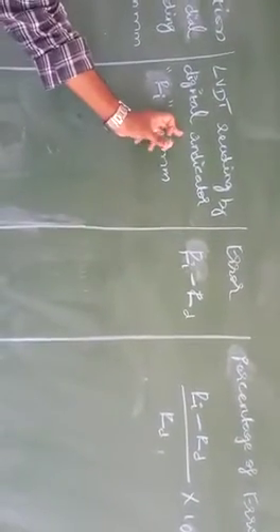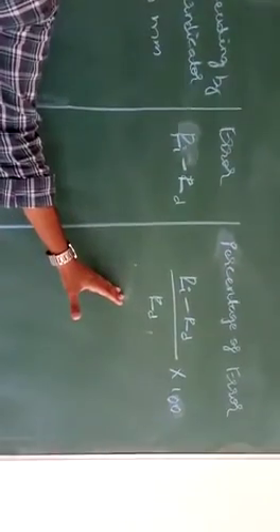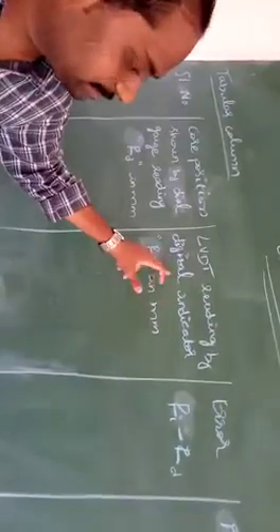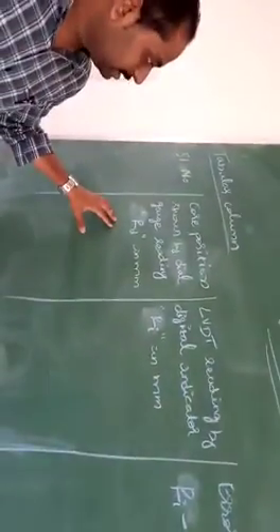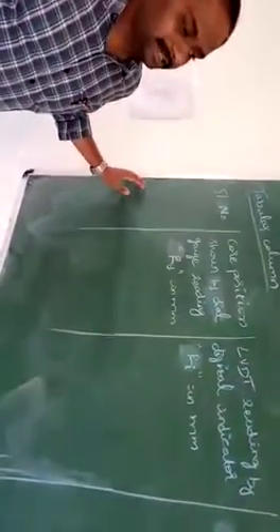Then the error, that is the difference in LVDT reading by digital indicator and the core position shown by dial gauge reading. And then finally the percentage of error, how much amount of error is there, you are going to find out by LVDT reading by digital indicator minus core position shown by dial gauge reading, divided by core position shown by dial gauge reading, multiplied by 100. You are going to repeat it for around 6 to 7 readings so that you can plot the graph.